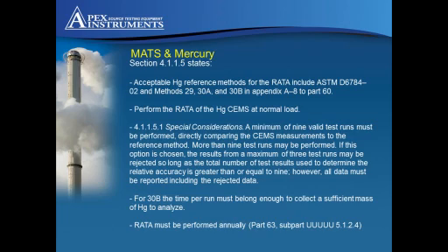That section of Part 63 on page 9502 states that Ontario Hydro, Method 29, Method 30A, and Method 30B are all acceptable reference methods for certifying Hg CEMS. We recommend performing a 30B, as in our opinion it is the simplest method, and taking into account that PS12B is based off Method 30B, it is the most like your sorbent trap monitoring system.